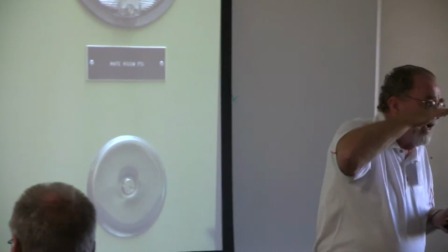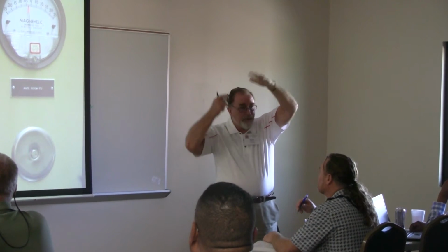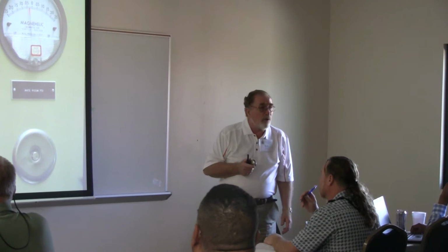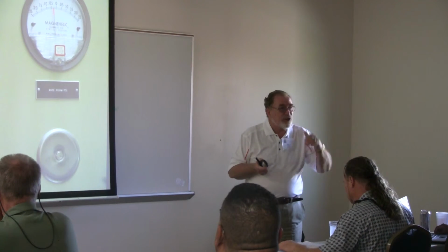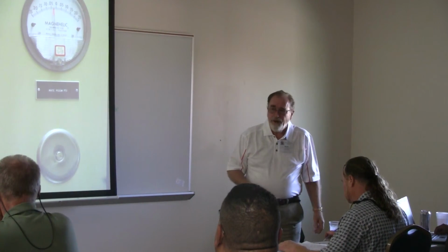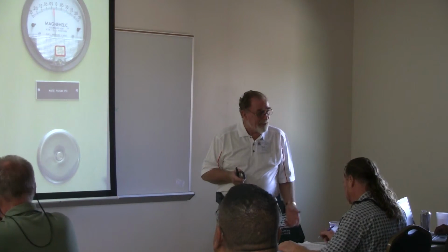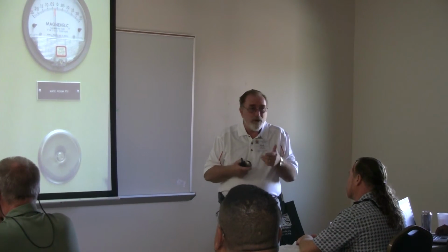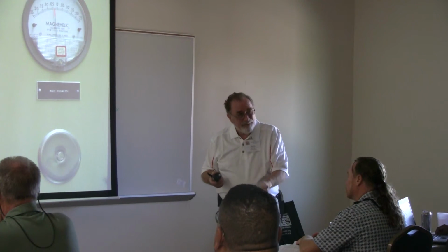Now, once it gets into the isolation room, you're supposed to take that air out and scrub it and clean it before you have it spewed into the air. And I taught a lot of these classes, and some of the older facilities have set these isolation rooms up, and they don't have a scrubber to scrub the air going out. And I said, that doesn't make me feel real comfortable going up on a rooftop unless I know that the bad stuff has been scrubbed out of the air. Or just don't put yourself in a position to be anywhere close to any kind of exhaust air coming out of the building.